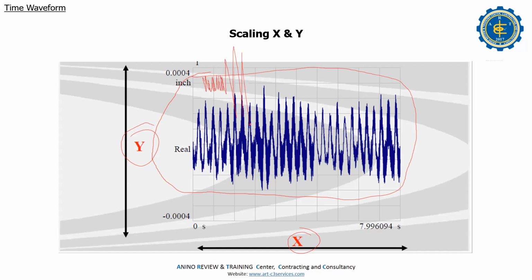And then impacting. You know, there is impacting. Yeah, impacting. But even in the spectrum, a gear fault you can also see in the time waveform. But if this is the spectrum, I don't like to analyze this one. I like this. If there is impacting, wow, good. There's impacting with the bearings. It's easy to make a report, right?